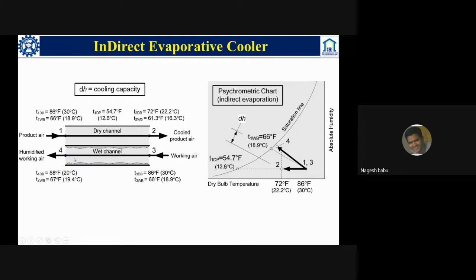In an indirect evaporative cooler, we have product air moving from 1 to 2. This is the outside air, and this is the cold air. But to achieve this cooling without an increase in humidity, we need another stream, the working air, which moves from 3 to 4. Here we divide the supply stream into two streams. One moves towards 4 and one moves towards 2. The air moving towards 4 is delivered outside the window, and the air moving towards 2 is delivered into the room.